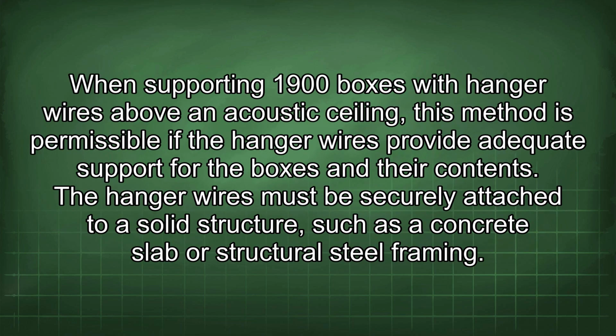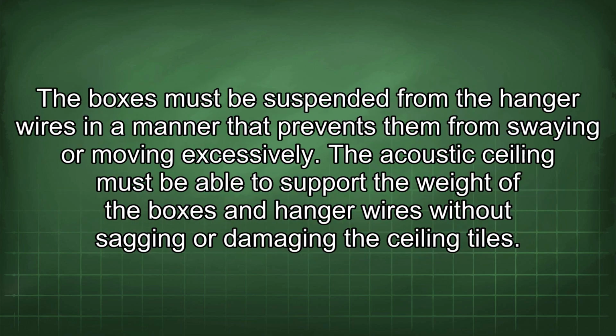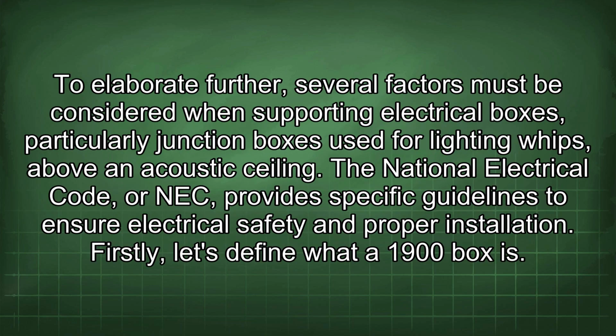314.23(a). When supporting 1900 boxes with hanger wires above an acoustic ceiling, this method is permissible if the hanger wires provide adequate support for the boxes and their contents. The hanger wires must be securely attached to a solid structure such as a concrete slab or structural steel framing. The boxes must be suspended from the hanger wires in a manner that prevents them from swaying or moving excessively. The acoustic ceiling must be able to support the weight of the boxes and hanger wires without sagging or damaging the ceiling tiles.